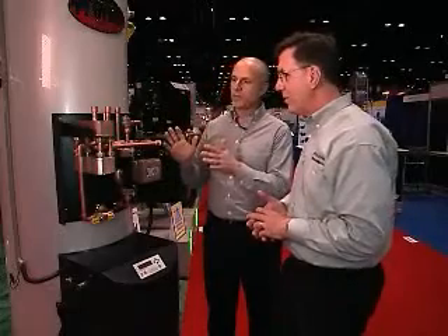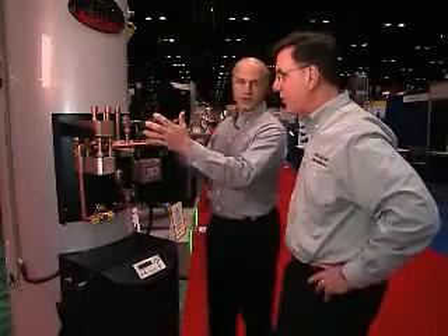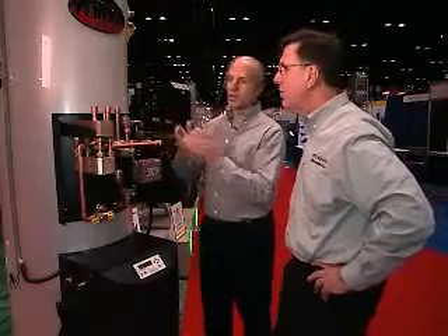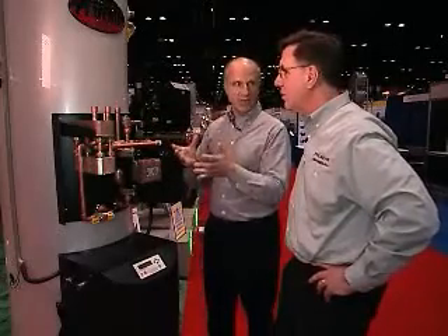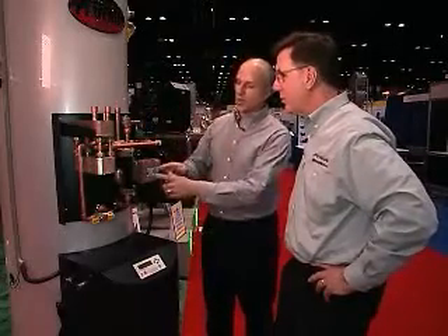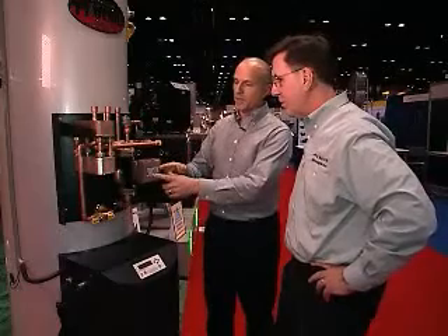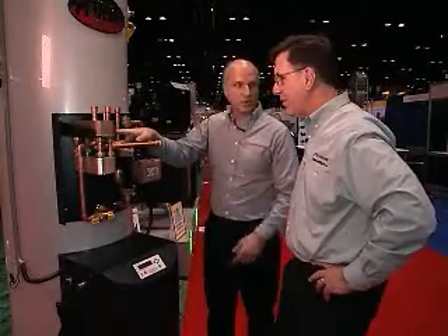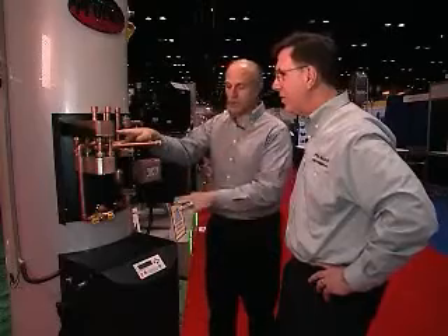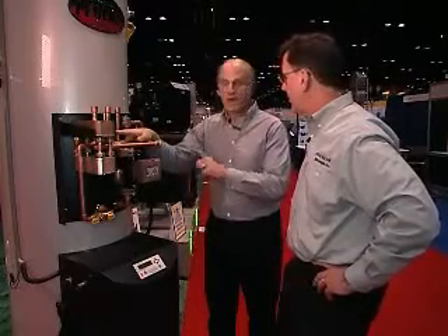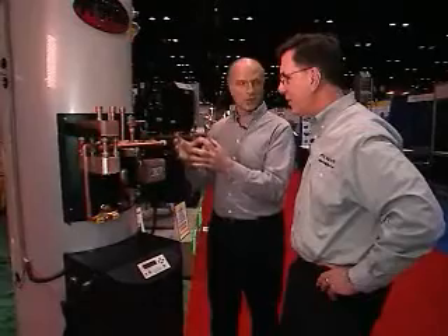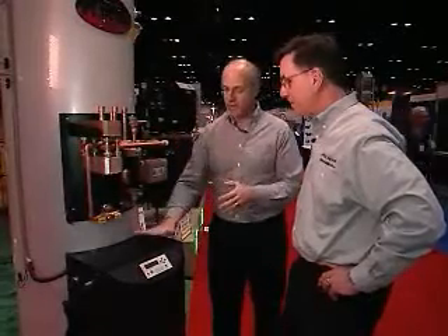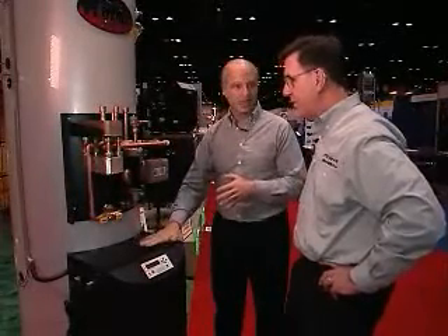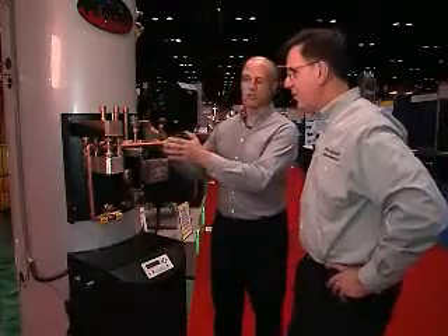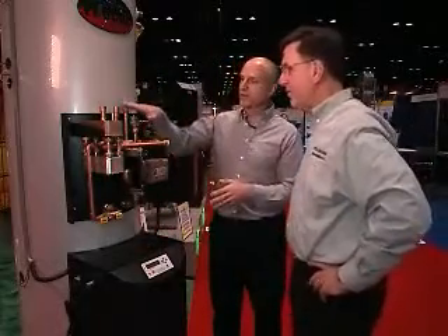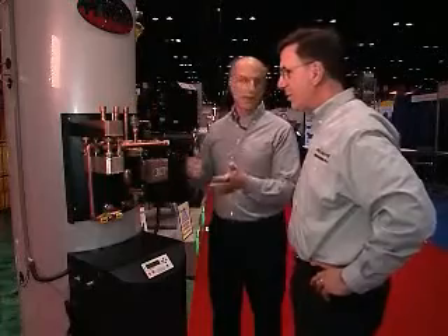The beautiful part about this is we've got a large volume of water, where we're taking the low mass of the system, which is in your space heating, and we're backfeeding it. We're varying the speed of the pump to maintain your set point based on outdoor temperature. This water heater actually has an outdoor sensor, so it works integrally. The system is always trying to keep the burner off as much as possible, utilizing the storage in the system to feed not only your space heating, but provide hot water at the same time.